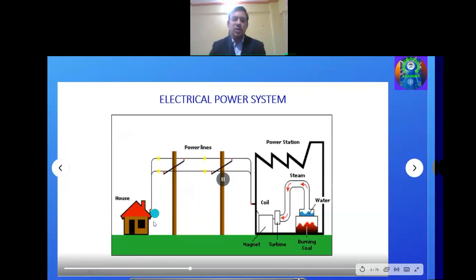Then what are the constraints of AC transmission? We know that when we transmit power over an AC line, if the distance increases, after a certain distance the power handling capacity of the AC line gets reduced because of voltage and stability constraints. As the distance increases, there will be a voltage drop because of the impedance of the line. Also, because of voltage mismatch or out of range voltage, stability constraints will also be there. Also power angle related stability. So there are so many issues. These are the constraints when we operate a power system with AC.